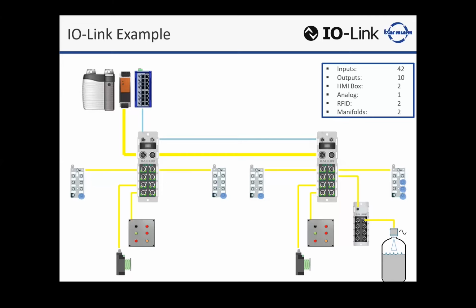So let's say those hubs were interchangeable on tooling. When that tooling comes and gets connected, that master block is looking for, I'm looking for my IO block A. And that IO block, in layman's terms, gets a report back, hey, this is IO block A or B, so that you can make sure you have the right device hooked up. So you can eliminate the need for either BCD identification or RFID in a very inexpensive way.